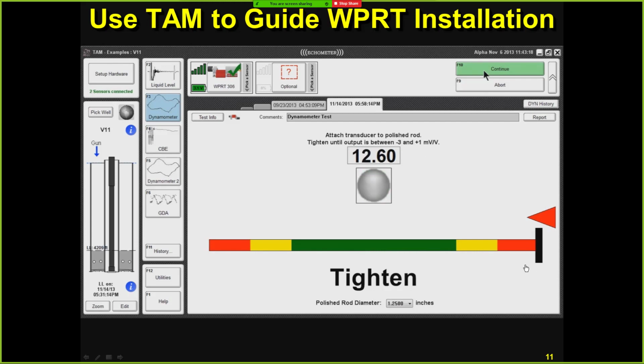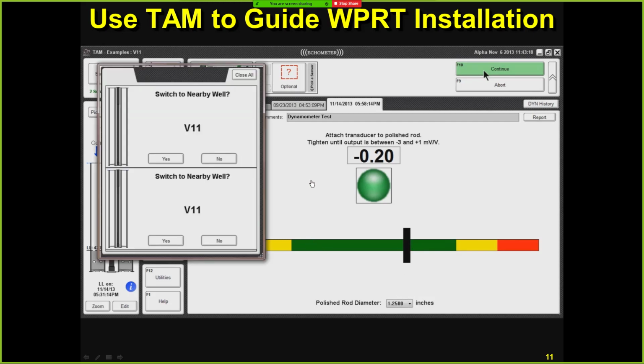And once this line gets in green, the wireless PRT will show a green light, and you wouldn't have to see this. But if you had a wired PRT using TAM, then it would work the same way as the TWM software just worked. And we'll see this line starting to reduce, get smaller. As you tighten up, the output's going smaller and smaller, getting close to zero. And once it gets to zero, it's going to move in the center of this bar, and you can say, aha, now I've got this line centered for this 1.25-inch polished rod, and I'm ready to start to acquire data.